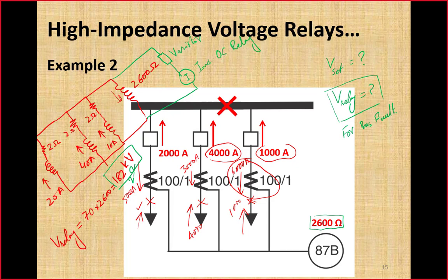So what is the purpose of this branch? If such a high voltage is going to build, this variable resistor or varistor resistance will reduce to 0, and instead of building high voltage across the voltage relay, that 70 ampere current would flow towards this branch and result in tripping of the instantaneous overcurrent relay. It means a high magnitude internal fault will result in tripping of the overcurrent relay instead of the voltage relay, and protect the voltage circuit or CT secondary circuit from getting a very high dangerous voltage.